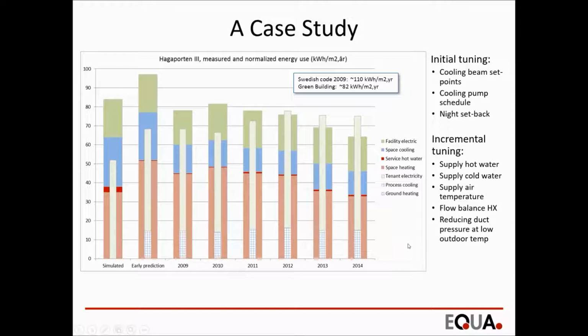What we did, after this early prediction, was take a number of tuning measures. We changed the set points for the cooling beams. We also changed the schedule for the cooling pump distributing the cold water in the building. And we also implemented night setback on the room heating system. And as you can see there, we managed to decrease the energy use by approximately 20 kilowatt hours per square meter a year. Now, I only count the facility energy because that's what's included in this requirement for the green building.